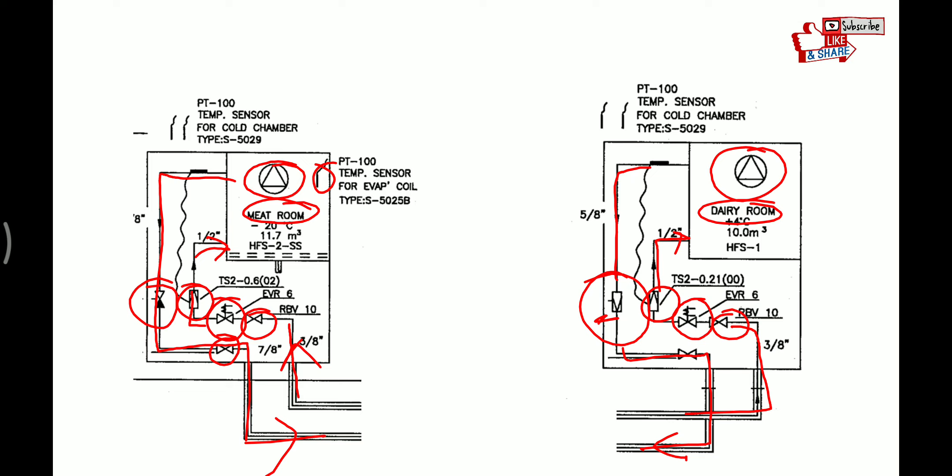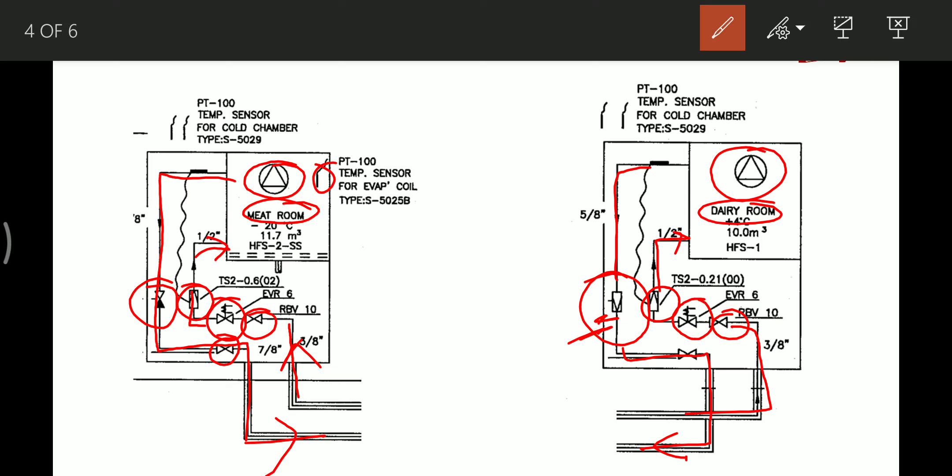I will now discuss two things in detail that make a multi-evaporator system different from a single evaporator system. The first is the back pressure valve. This back pressure valve is a spring-loaded non-return valve fitted at the exit of the refrigerant from the evaporator whose temperature is to be set higher — for example, the veg room and dairy room at 4 to 5 degrees, compared to the meat room and fish room at minus 20 degrees Celsius.